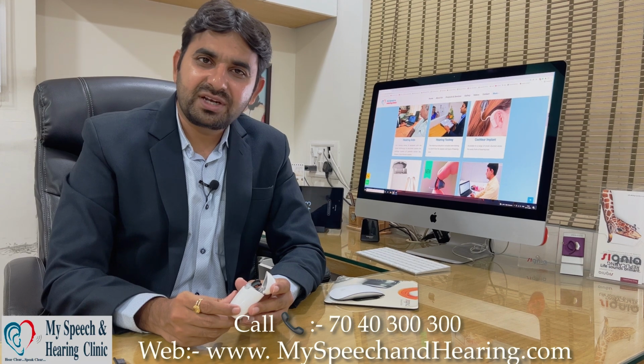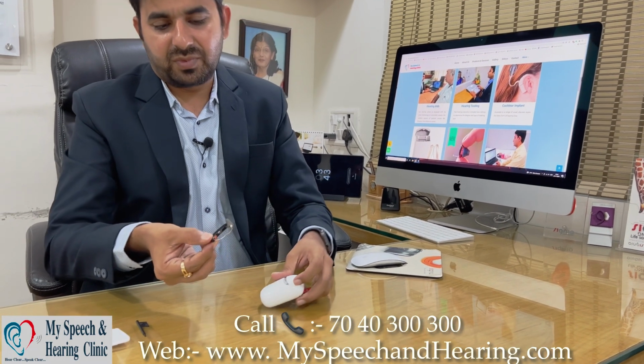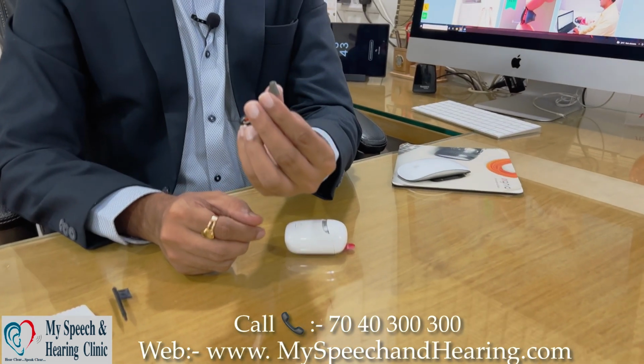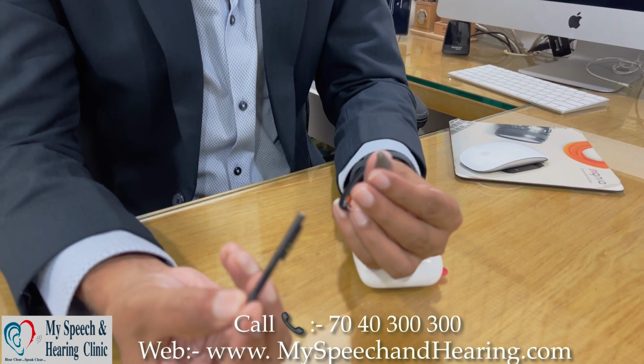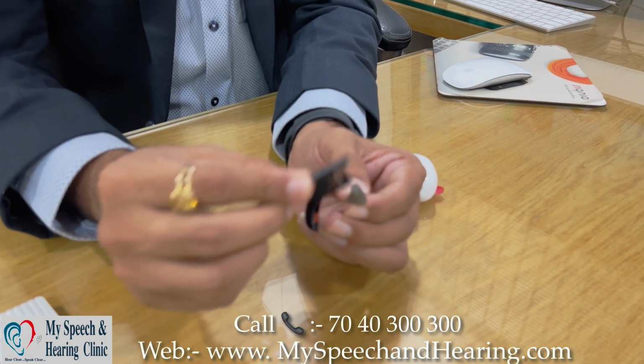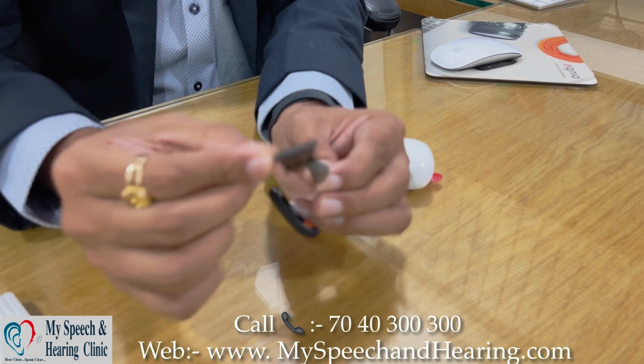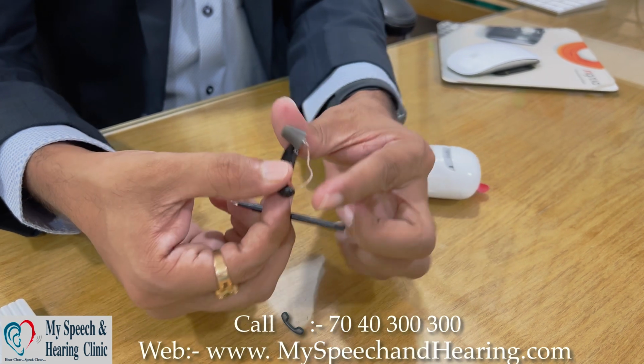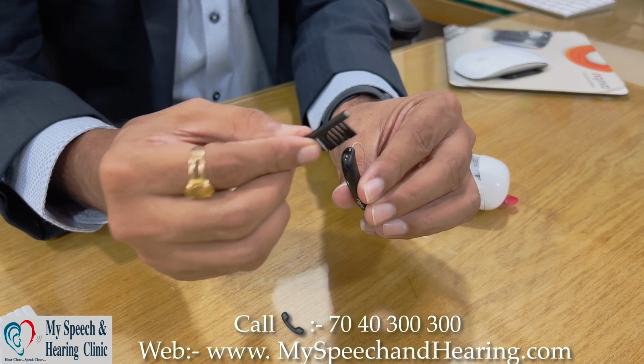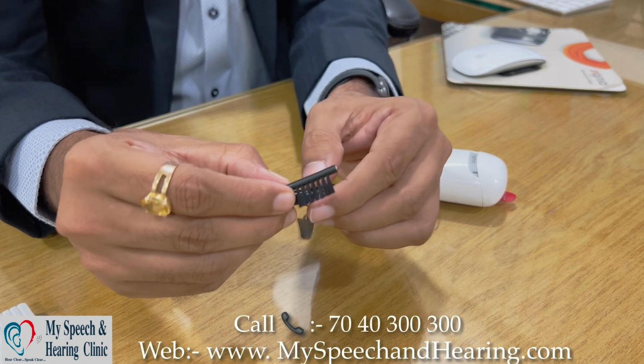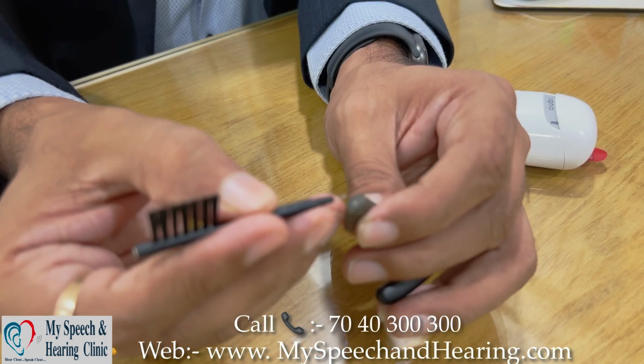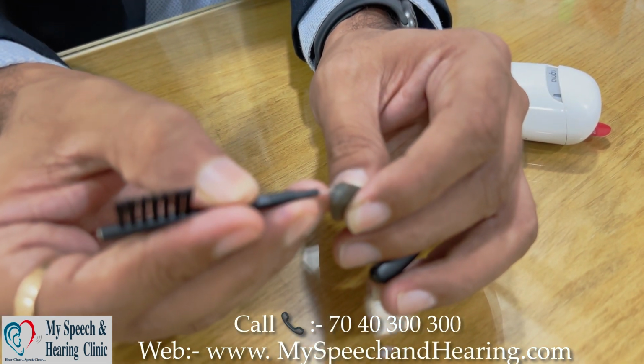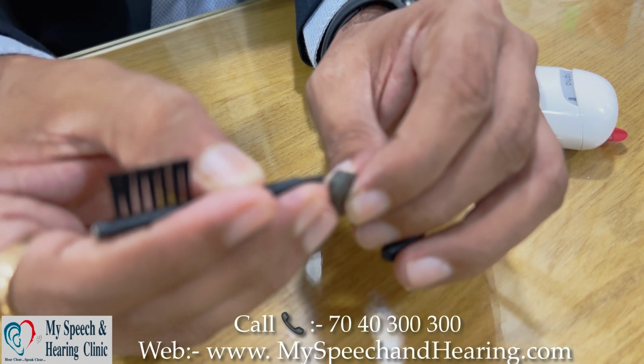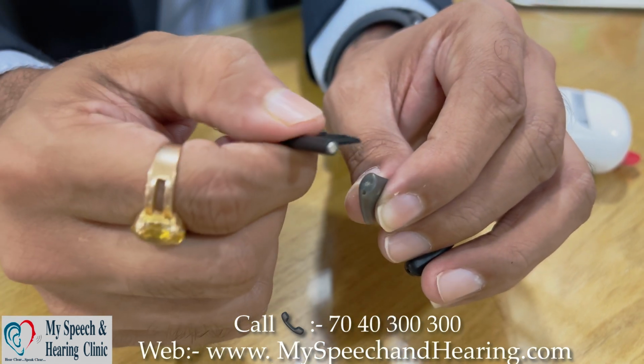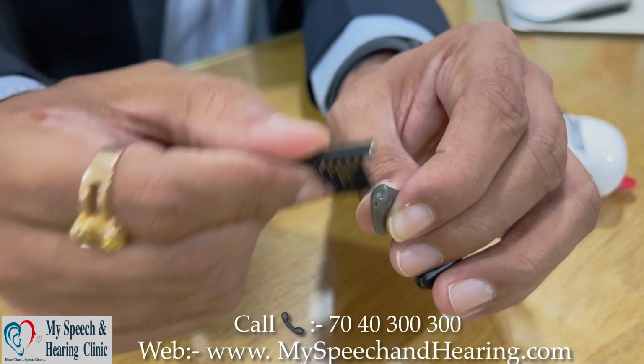So now let's see how we clean the hearing aid. In order to clean a hearing aid, the first thing you can do is use the brush which is provided in the box. You can clean the sleeve like this from all parts, from all the corners. Also you can clean the hearing aid like this, the microphone area which is here. Also you need to clean an important part, which is this area. This area can be cleaned like this using this pin. This is the part where usually you will find the wax accumulation. The moment you clean this part, you will also start hearing better. So that's how you can clean the sleeve.